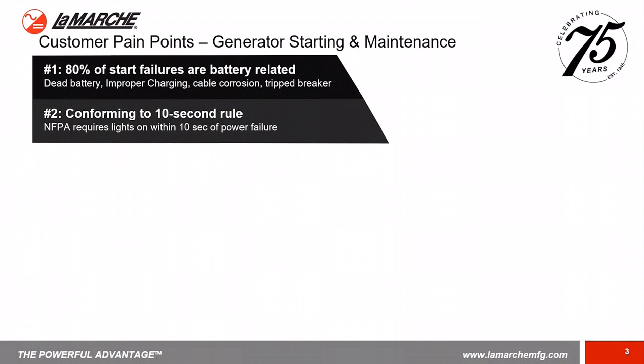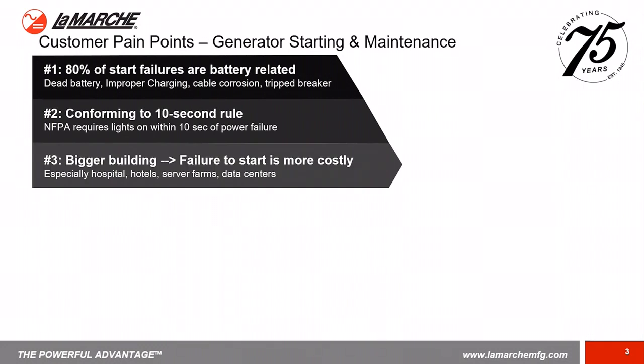Number two, conforming to the 10-second rule per NFPA requirements. NFPA requires that all generators ramp up to speed and provide the proper output within 10 seconds of a power failure.